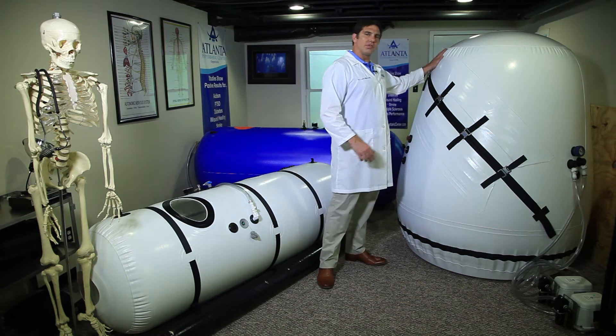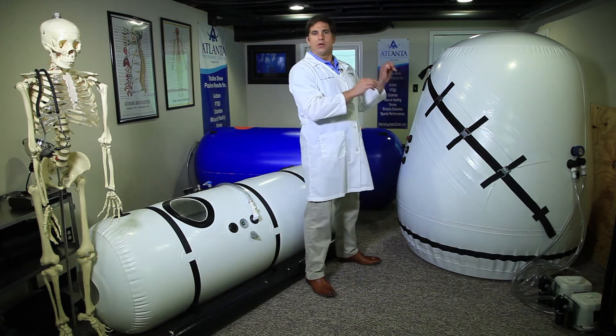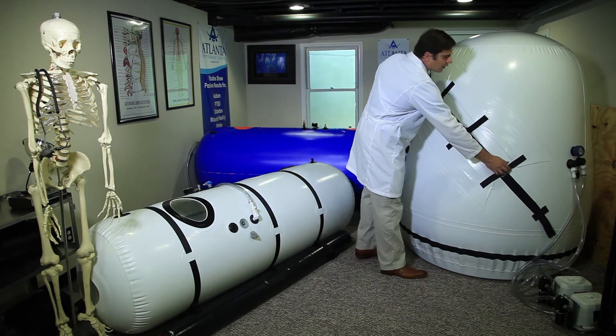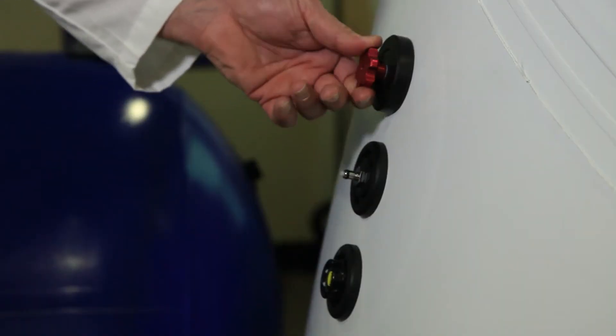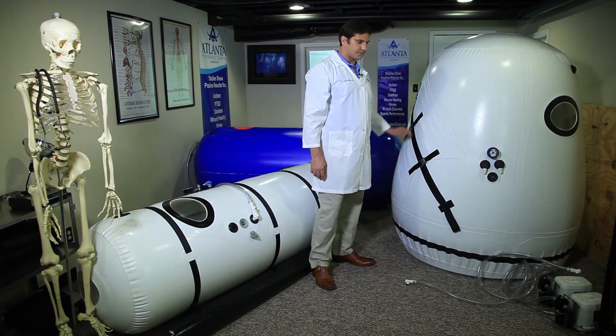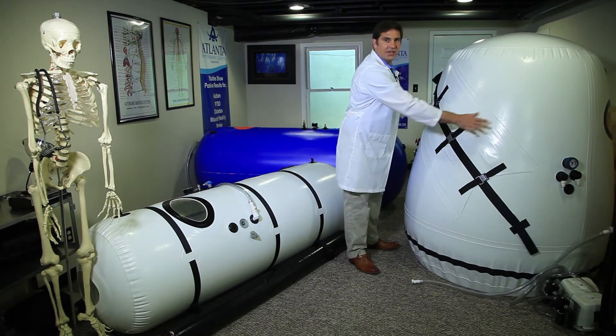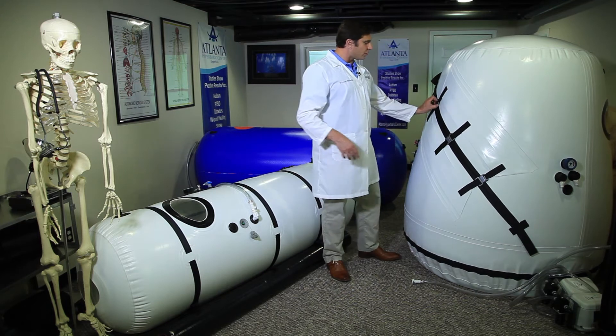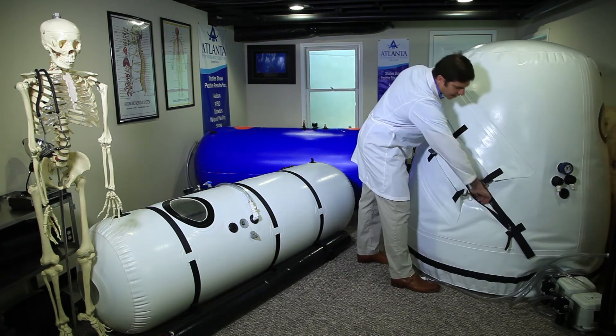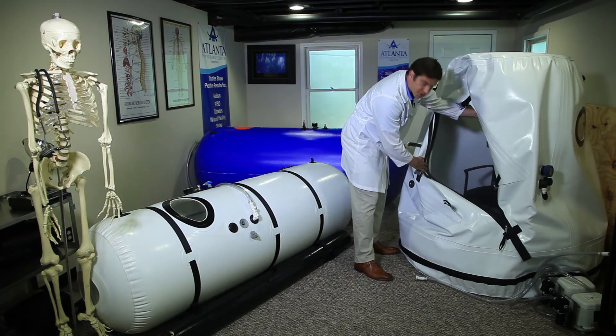If we have an emergency — a patient renders unconscious, has a panic attack, seizure, or falls asleep and needs to be extracted — all we have to do is open the valve and release the hoses. You can even instruct a conscious patient to use their fingers to assist. Literally within about 15 to 20 seconds, I am able to get a patient out of this hyperbaric chamber safely and efficiently without any problems at all.